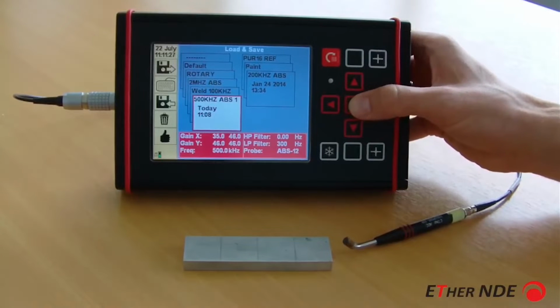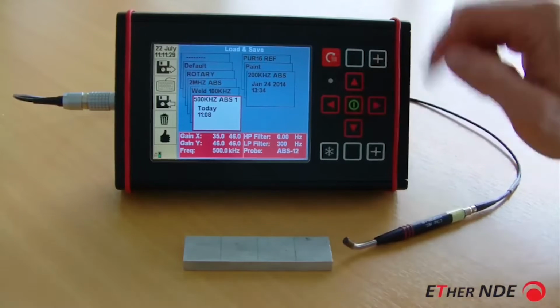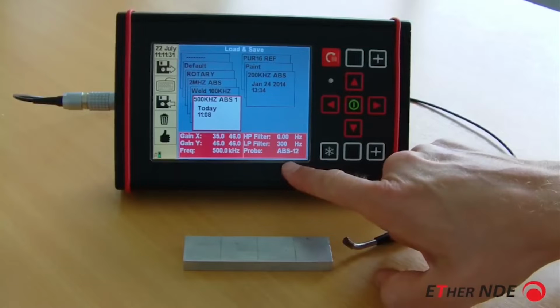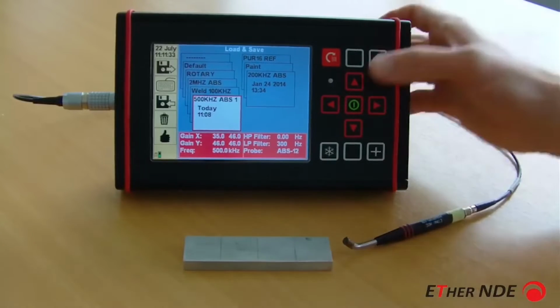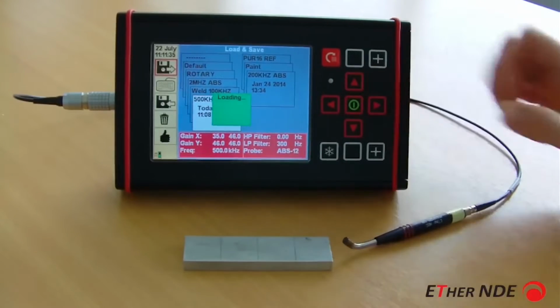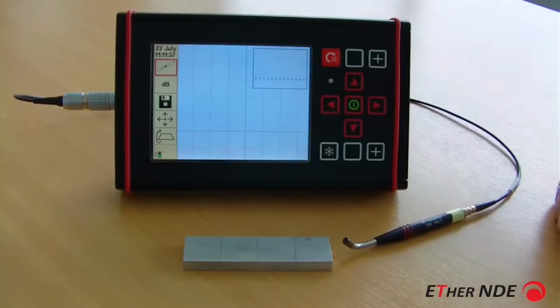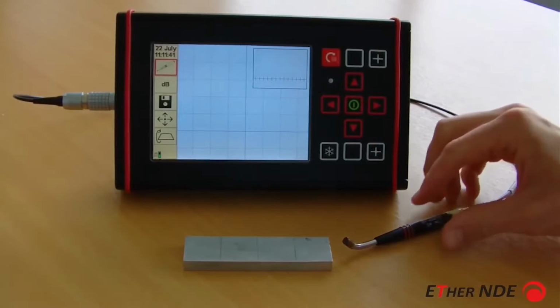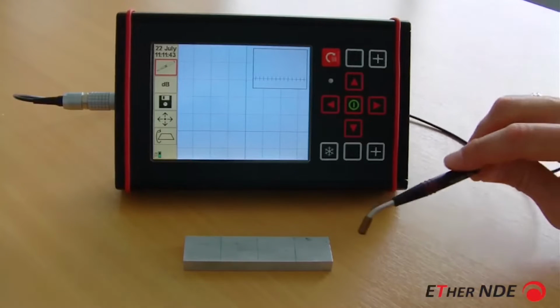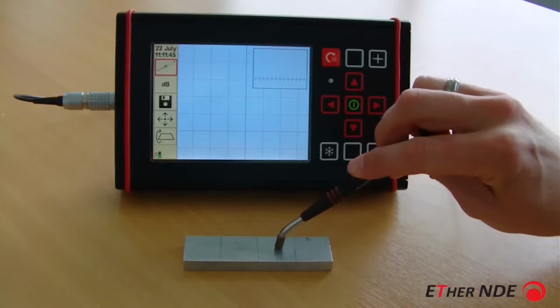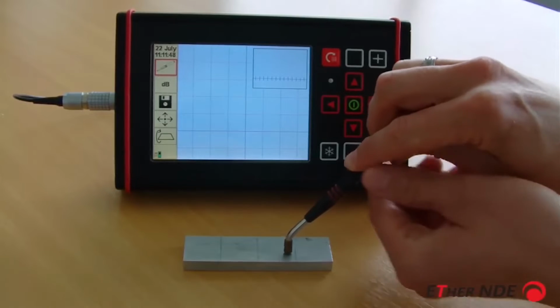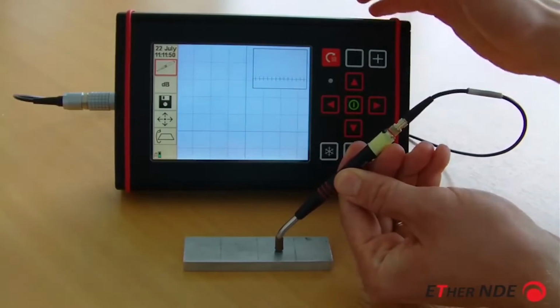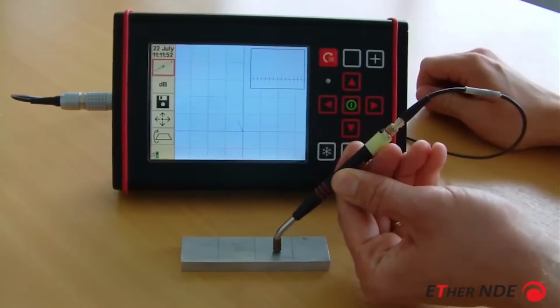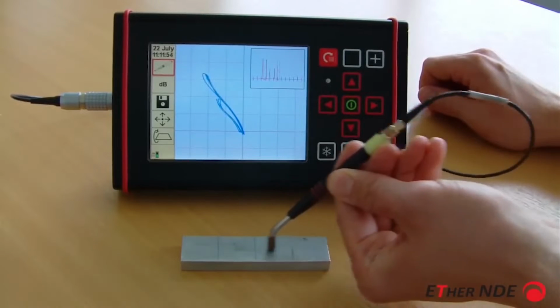By pushing the OK key, I can now see at the bottom here that this is set up to use an absolute probe in the 12-way socket. So open the setting. So the instrument is now configured to use the probe. So first step, make sure everything's okay. Put the probe on the test piece, which is a piece of aluminium, and do a balance. You see, it's alive.